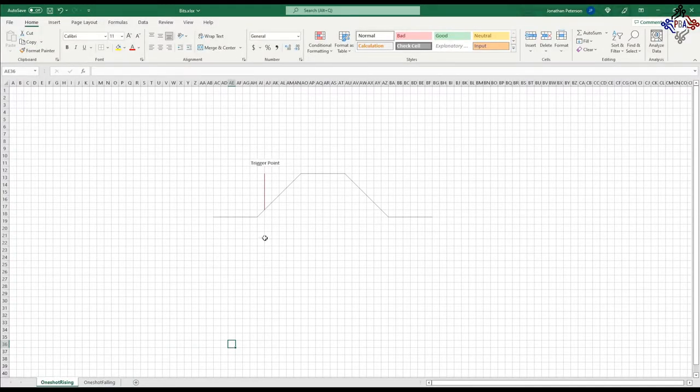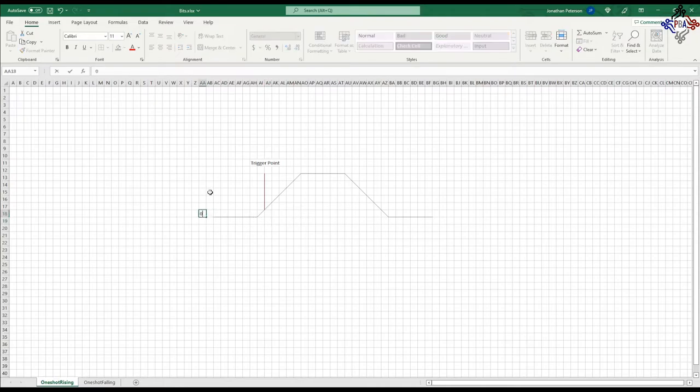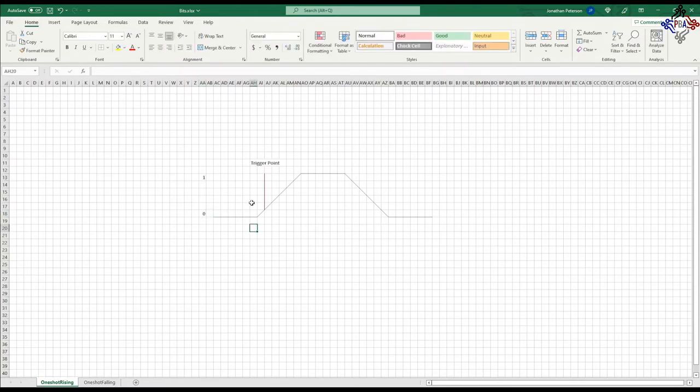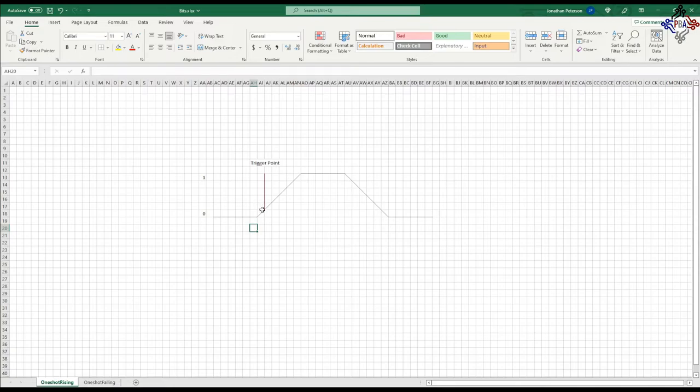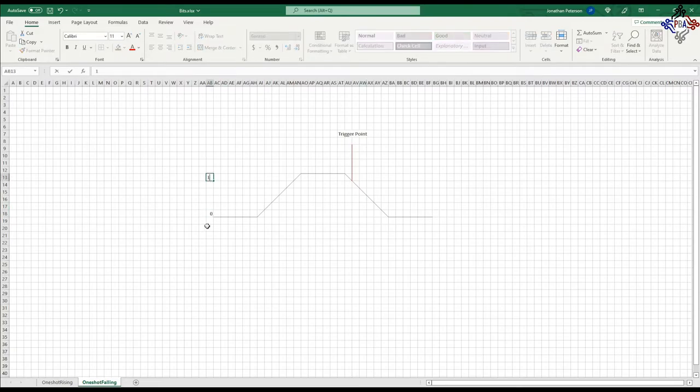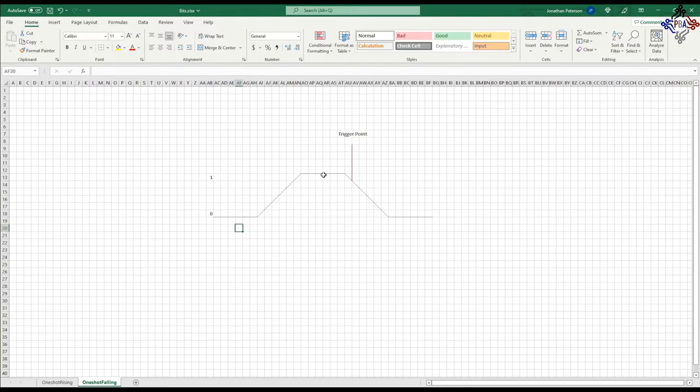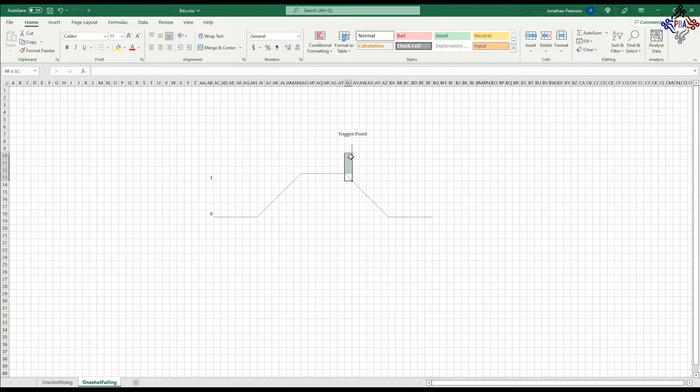For a one shot rising, this is going to simulate us pushing a button. We start at zero down here, and then we press the button, and we've got one up there. Just like in our tags. The one shot rising looks at this line. As soon as it sees you start to push a button, it sees a rising edge coming in. It turns on whatever the output is right there. A one shot falling, once again, we got our zero, we got our one. As we push the button, if we were to hold that, say for half a second or one whole second, and then when we let it off, it looks for the falling edge of that one shot, and it triggers at the falling edge.